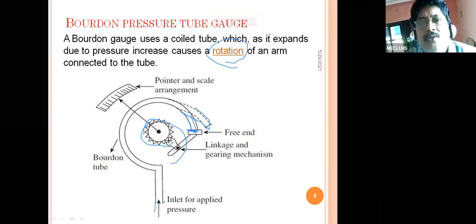Whenever the bourdon tube rotates, elongates, or expands, the connecting rod also moves. Thereby, the rack and pinion arrangement moves, clockwise or anti-clockwise depending upon the pressure, and the needle deflects on the scale, showing the reading of the pressure. It's a very simple arrangement. Do you understand this pointer and scale arrangement?